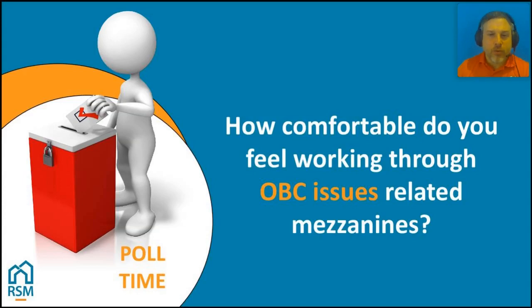You have to go through a particular story in order to get to the answer. In order to know how many exits, I need to know if I need a vertical fire separation. How do I know I need a vertical fire separation? Well, I need to know whether it's considered a story. So you have to work through these issues in order. And if you don't, then it can get quite confusing.